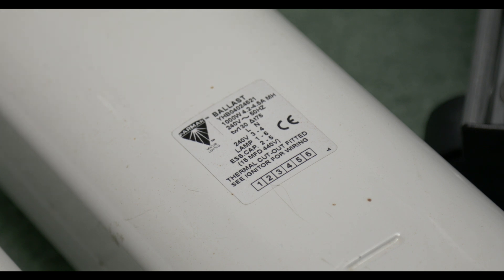There's two types of metal halide lamps: you've got the low voltage types, which is normally below a thousand watts, designed to run on 240 volt mains. Then a thousand watts and up, you normally have the high voltage type, which is designed to run between a couple of phases on 380 to 440 volts.